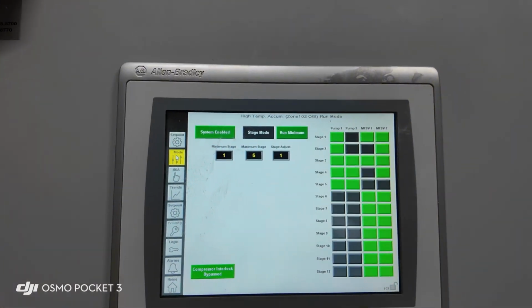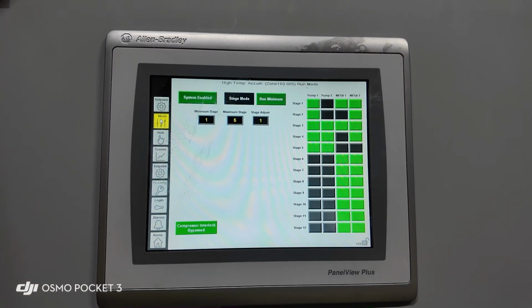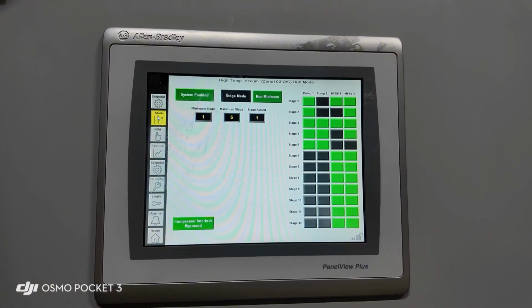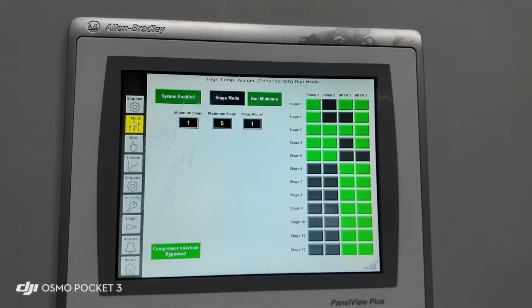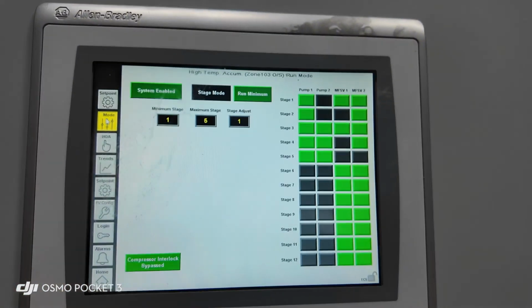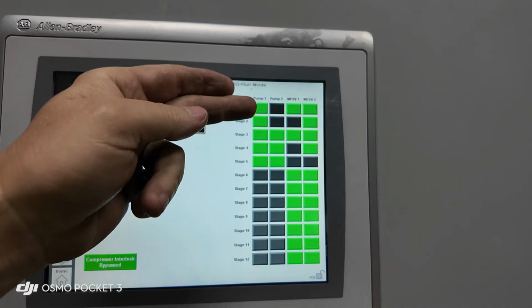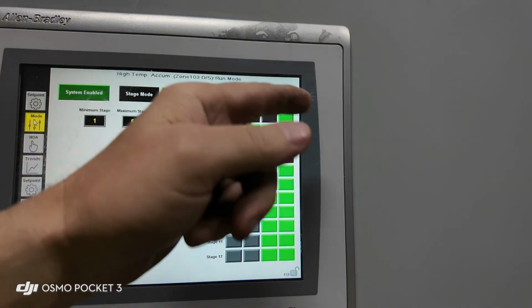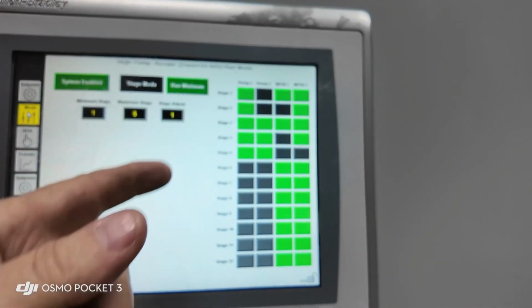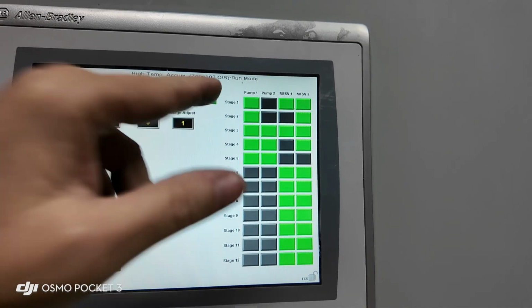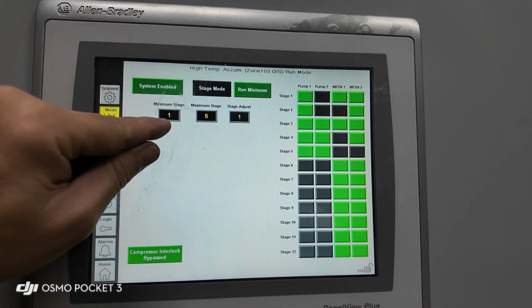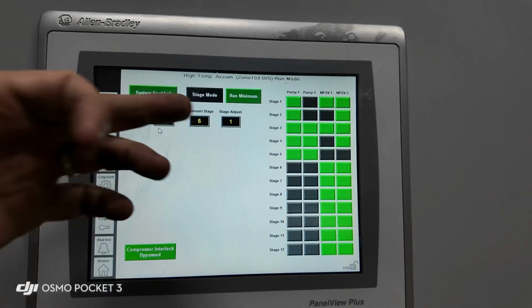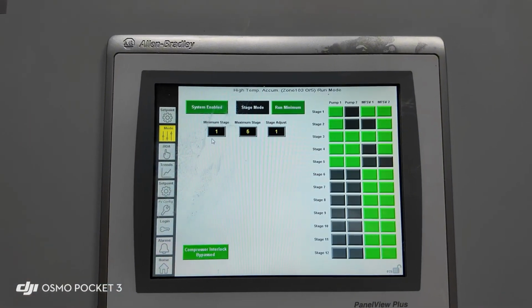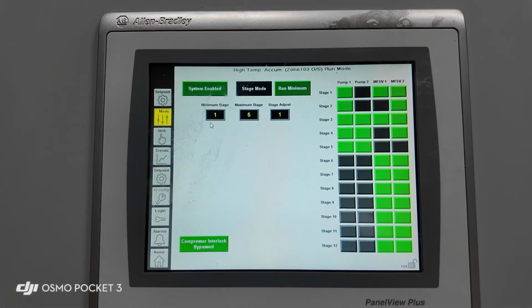This is system enable. Nothing will run on this vessel package, pumps, nor makeups, if it is not enabled. We can select stage mode, which allows the pumps to operate through a series of stages of minimum flows on and off, or pumps on and off. I have it in the run minimum, which is only going to allow it to be in stage 1, and it won't stage adjust. Okay? Normally, we would be in a stage adjust with our maximum setting of stages.